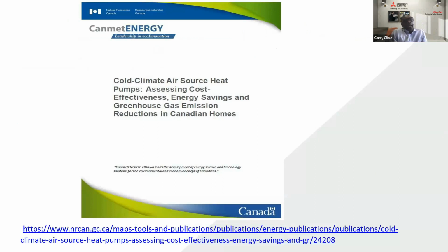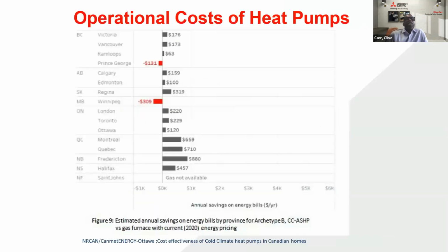To better illustrate what we have known and what we've seen in the test results of our system, the overall operation of the heat pump system throughout the heating season leads to an operating cost that's equivalent, slightly above, or slightly below natural gas. Natural gas was one of the benchmarks because at this given time, it's one of the cheapest forms of energy to heat your space.